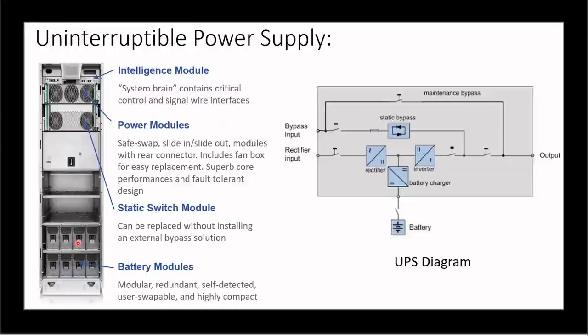So here you can see that the UPS is there in the module forms, right? This is the power module, this is the static bypass, this is the maintenance bypass. But before coming to the modularity, the UPSs were not in the modular form, they were standalone. So there were no modules.